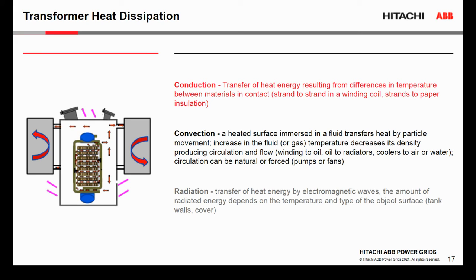A similar phenomenon we see between the radiators or coolers and air. So radiators having higher temperature increase the temperature of the surrounding air, and with higher air temperature, the density of air is reduced, and then we have better circulation. We produce circulation around the radiators. And radiation is basically the transfer of heat energy by electromagnetic waves, and we transfer energy with radiation from the tank and from the cover.